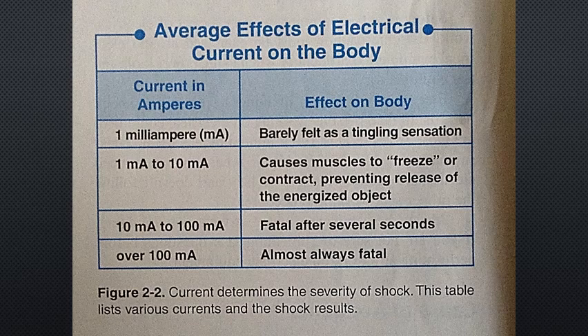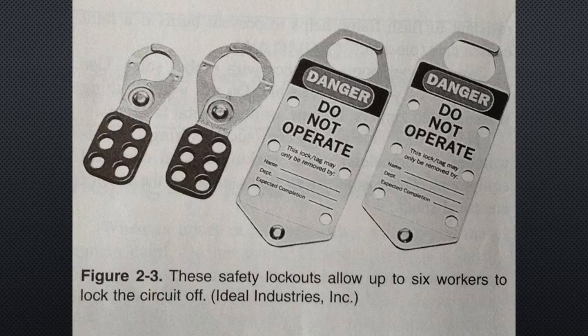The best way to prevent electrical accidents is to always de-energize the circuit before working on it. When you disconnect the circuit, tag or mark it so it is not mistakenly reconnected before you complete your work. Lockout/tagout procedures involve placing a lock on the disconnect to prevent the circuit from being reconnected. When work is completed, the lock is removed and the circuit is re-energized. Be aware of any specific lockout/tagout procedures and follow them.